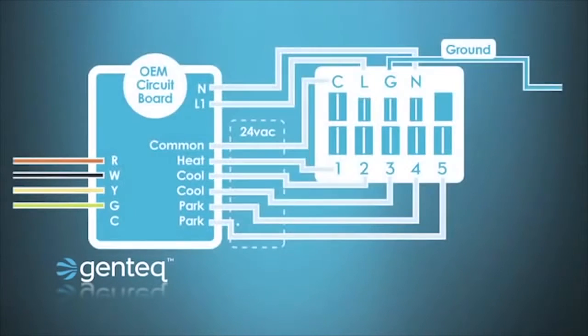Here we see an example of an HVAC system with an X13 motor. This is a 115 volt system. It's got line 1 and neutral connected to the motor, and it has all 5 taps of the motor connected to the OEM circuit board.